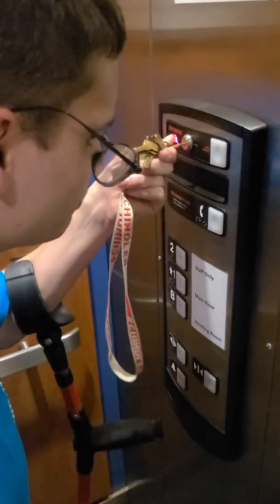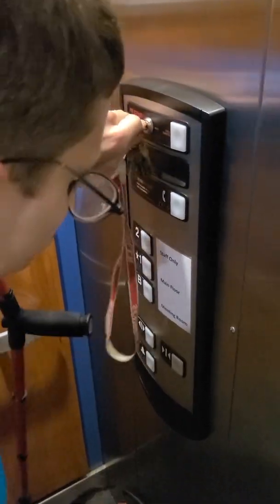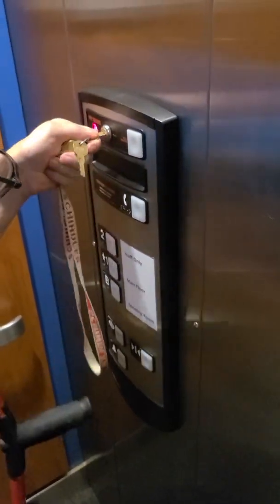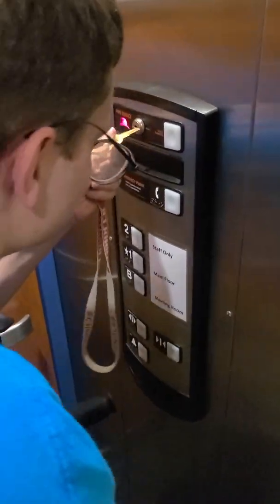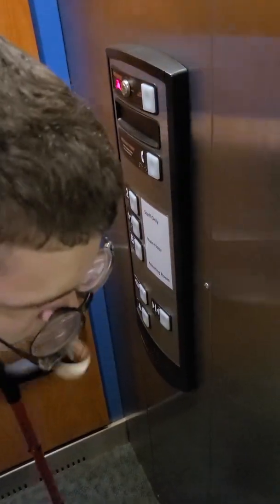The elevator is going to stay here anyway. But if you want to hold it at the floor, put your key and put it on hold — that way no one downstairs can send it anywhere. But if you want to send it out to another firefighter, turn it to off and it's going to go back up to the recall floor.